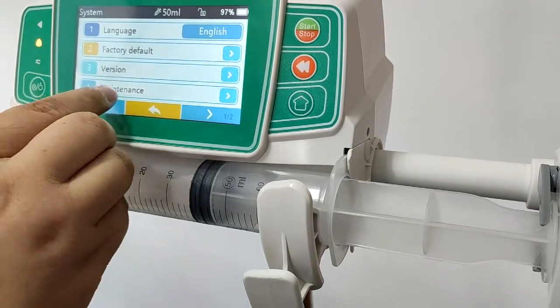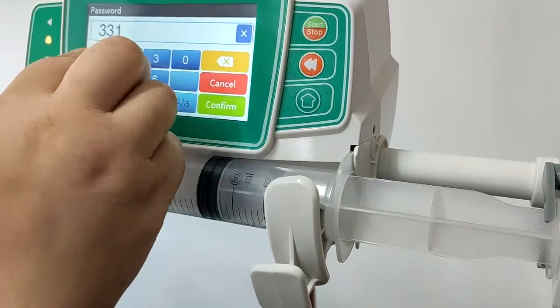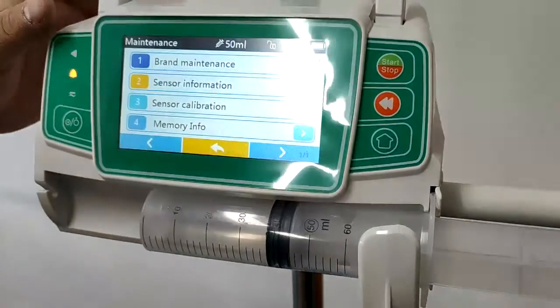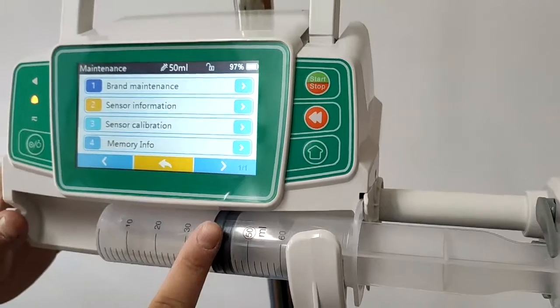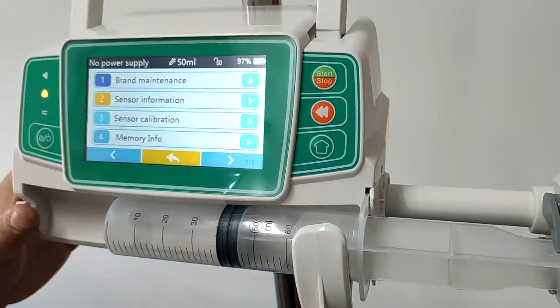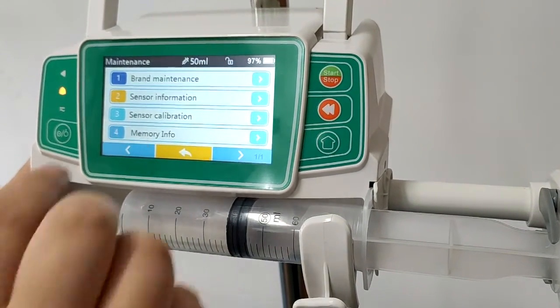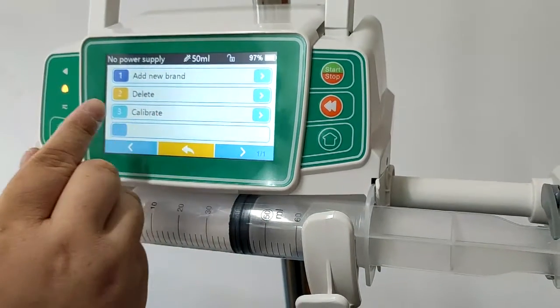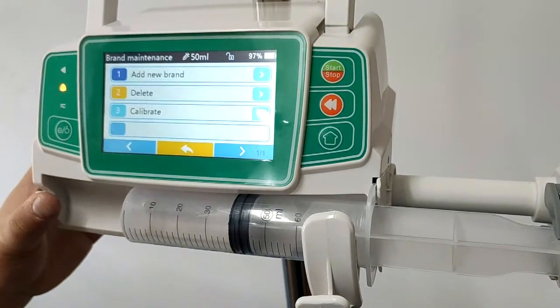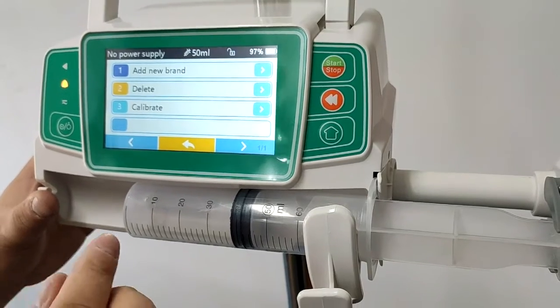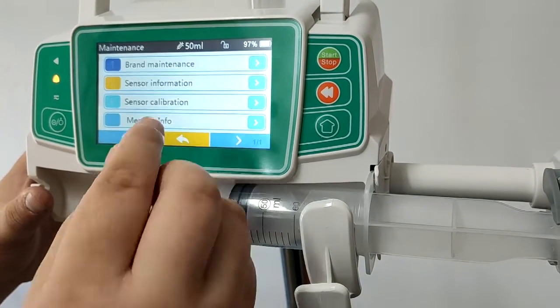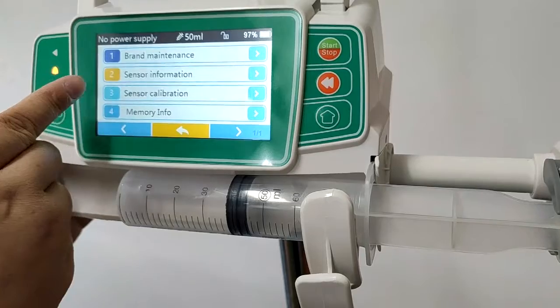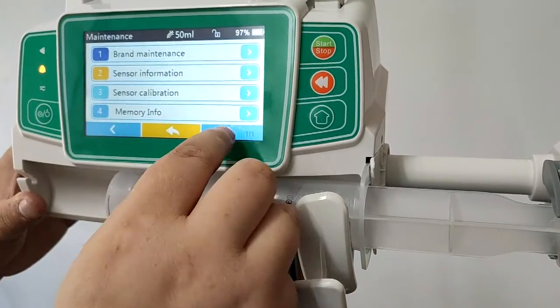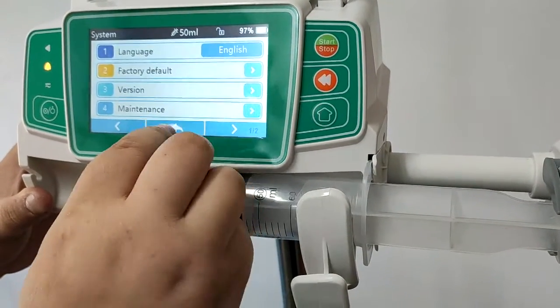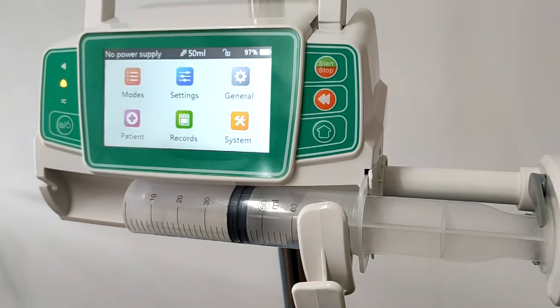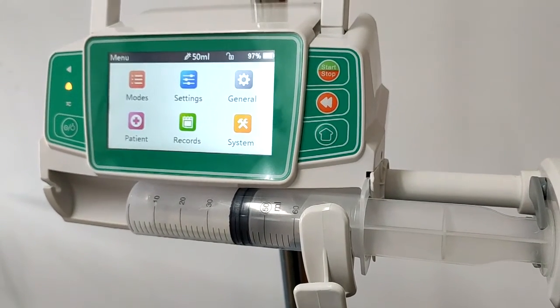By the maintenance, you will need a password with 3312. Here, you can calibrate the syringes into the pump. If you want to use a different brand of syringe, you can add a new brand, delete or calibrate. For more details, you can refer to our video of how to calibrate the syringes to a pump. And also, you can find the sensor information, sensor calibration, and the memory information. Okay, we have finished the introduction of the pump and about how to operate the pump. Thank you.